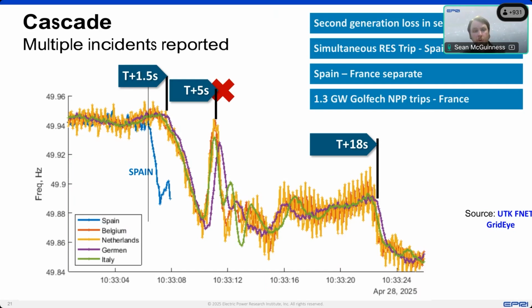One thing to address also is that you'll see here that the frequency measurement in Spain disappears at 10:33. This is essentially when the PMU went offline, so that's when it lost its voltage or lost supply. We don't know if it was on a feeder with under frequency load shedding, or on a feeder that was just disconnected, or some other abnormality. We don't know, but we do know that it lost supply. We have no measurements after that point, so we don't know exactly what happened in Spain after that.